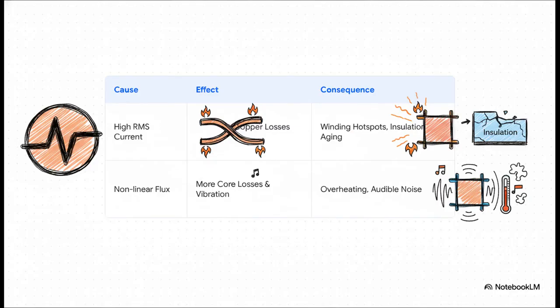This table really shows you the chain reaction. That massive spike in current causes a huge increase in what we call I²R losses. That's just a fancy way of saying the copper windings get incredibly hot, creating dangerous hotspots that rapidly cook and age the insulation. At the same time, that chaotic nonlinear flux causes the core itself to heat up and physically vibrate, creating a loud, ominous hum and putting the whole structure under mechanical stress.